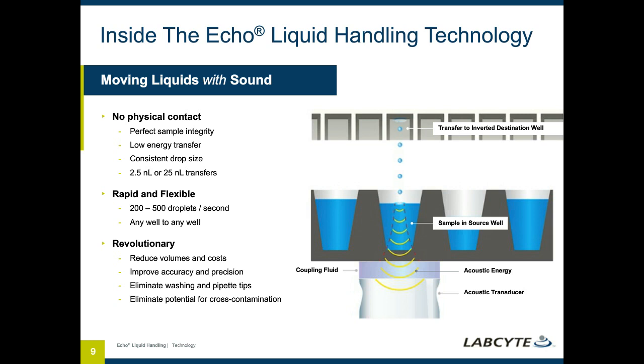And through the focusing of that acoustic energy at the surface of the liquid, we can very precisely and very accurately eject either 2.5 nanoliter droplets or 25 nanoliter droplets, dependent on the instrument, as I described in the previous slide. And this has enabled our customers to really revolutionize the way that they do science, both by reducing the volumes of the reactions they do and of course, the costs associated with those, and to perhaps in many cases, more importantly, improve the accuracy and precision of those assays. It eliminates any washing or pipette tips, and I'll go into some detail in terms of what the benefits of that are, and eliminates any potential for cross-contamination that a tip-based liquid handler always has risk of.